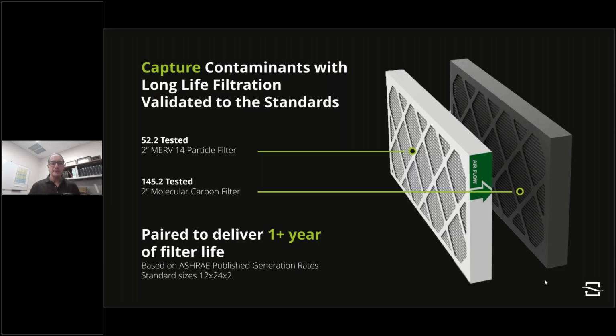And that had to meet a test known as 145.2, which is relatively new, and what really pushed this into the mainstream, if you will, of acceptance, why the articles are being written. It also now is adopted. This standard, this IAQP, has now been adopted under USGBC's LEED version 4.1 and now version 5. All of this is because now they can see, hey, look, in the interest of decarbonization, but also in the interest of better air quality, we can do this where you apply the right sets of tools and the right technology that meet the right standards. However, if done in the way in which we're managing it, we can extend the life of those filters for greater than a year.